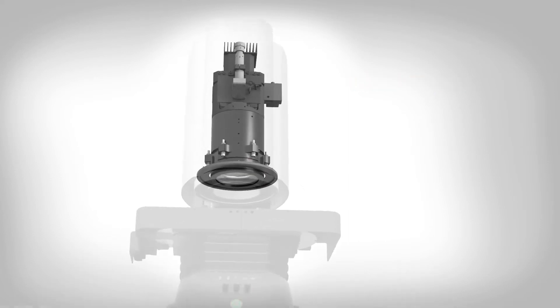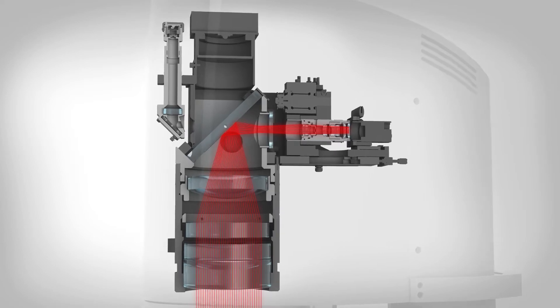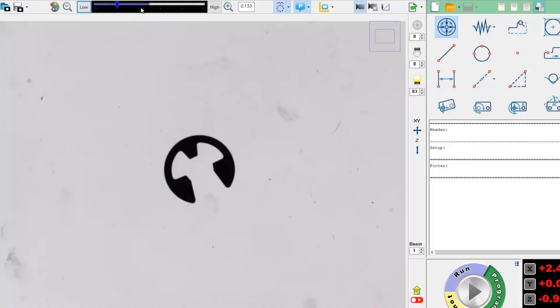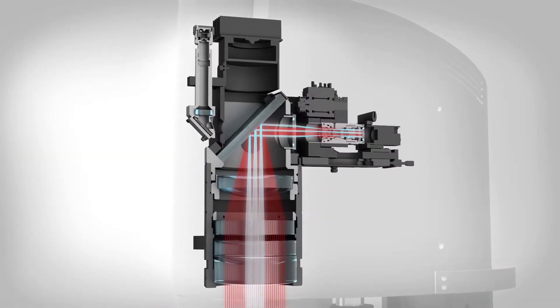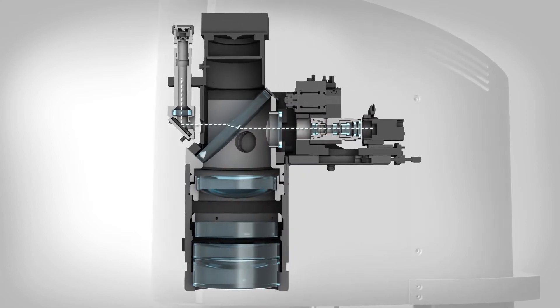Dual magnification optical systems allow operators to view entire parts or multiple parts using the 100 millimeter field of view. By switching to high magnification, optical precision is increased for accurate measurement of smaller features. Both magnifications feature the same working distance for each lens, resulting in a fully telecentric parfocal image.